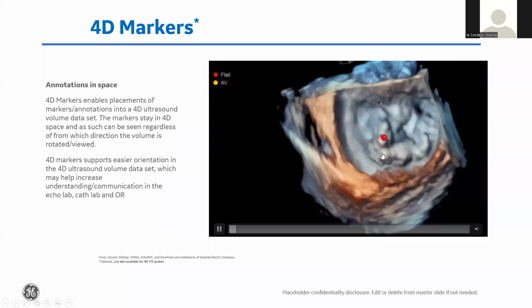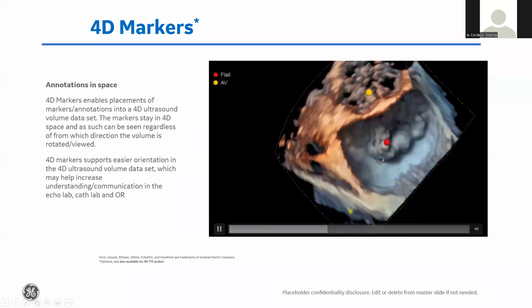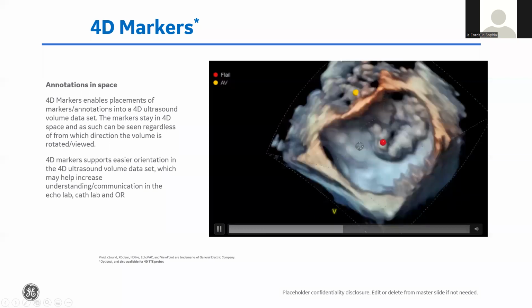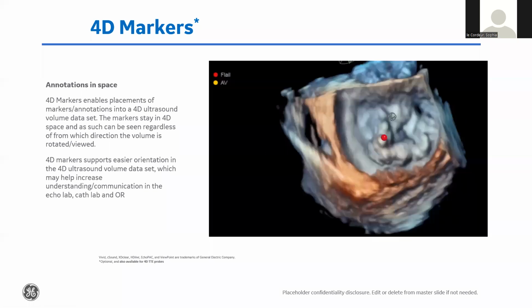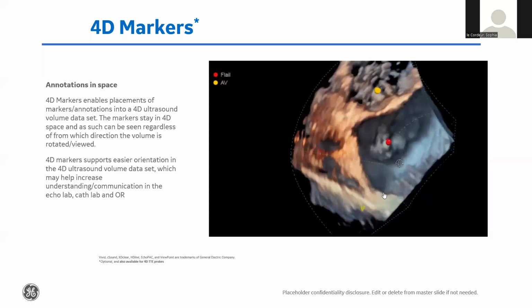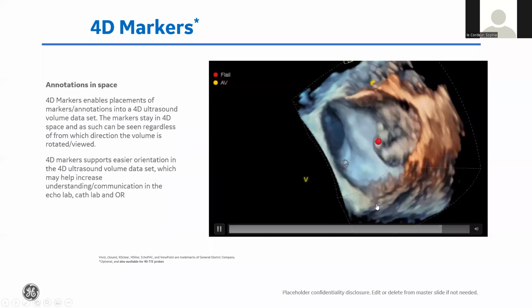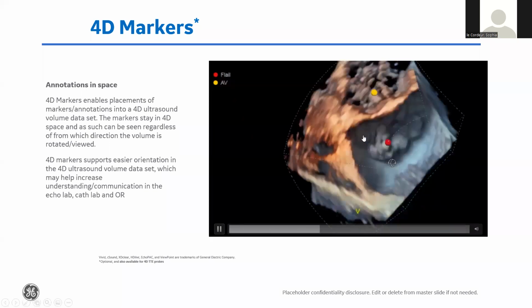However, look at this surface rendering, the way we are visualizing this surface. Again, remember in 3D, yes, we are looking at a 3D volume, and we are doing surface rendering of a 3D volume shape. However, we are displaying it on a 2D monitor. So something has to tell me the depth perception, which one is near, which one is far. This is where most of the time it's usually yellow and gray. But here, with what we call HD color visualization, HD live visualization, nearer structures are shown in yellow. Further structures are shown, or further anatomy is shown in blue.